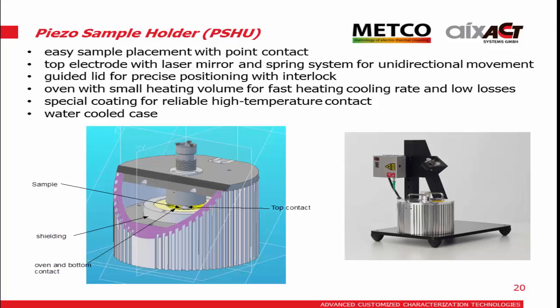They have a very small heating volume, and the sample can be easily placed inside and establish the point contact to the sample from the top and the bottom. And we measure on the top by a single beam laser interferometer on the top surface by a rod, basically, which has no big force, so that we are independent of the electrode materials. So, for example, silver paste or a degradation of the electrodes or planarity does not have a big effect here. It's mainly a matter of precise sample placement, and it can also maintain a fast heating and cooling rate to speed up the test in this setup.